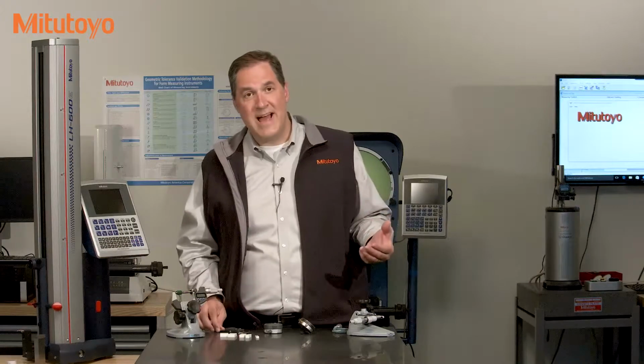But calibration takes time and costs money. And since different organizations have different thresholds of acceptable risk, there's really no perfect or best calibration method. A good calibration method will quickly search for errors and give a sufficient likelihood that the measuring equipment is either good or bad for its intended purpose. A good calibration method is a well-engineered test that finds the optimal balance between cost and risk.